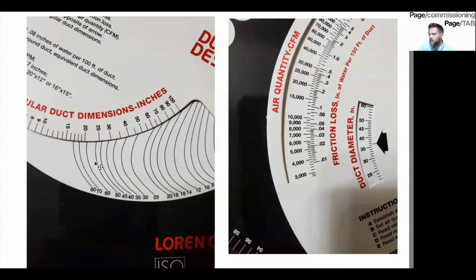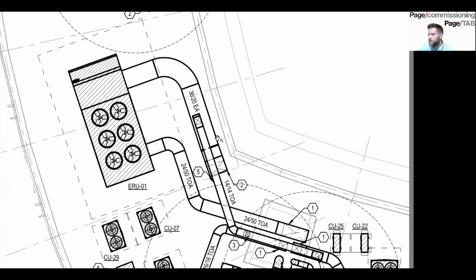So we'll go to our ductulator and line that up. So we have a 24 by 50. So here's 50 roughly at the 24 line. And then we look at what 0.08 can do, and look just above 11,000 CFM. So it's sized correctly. So we only have an issue on the exhaust side, but we caught it, right? And hopefully we caught this before the shop drawings came out and they've already ordered ductwork, right? But more importantly, before they start installing it.